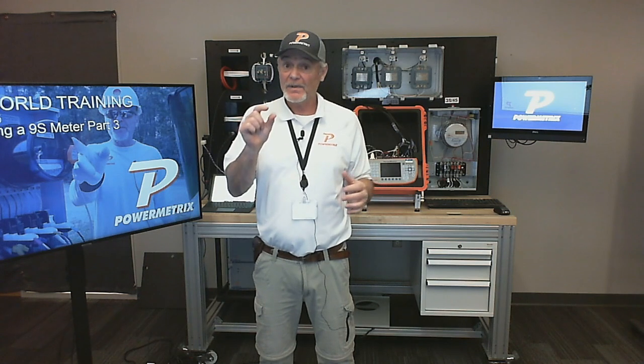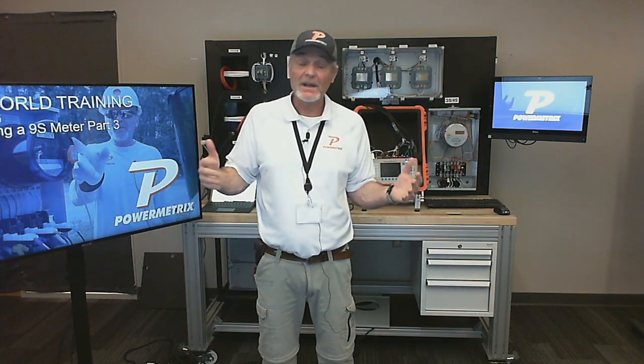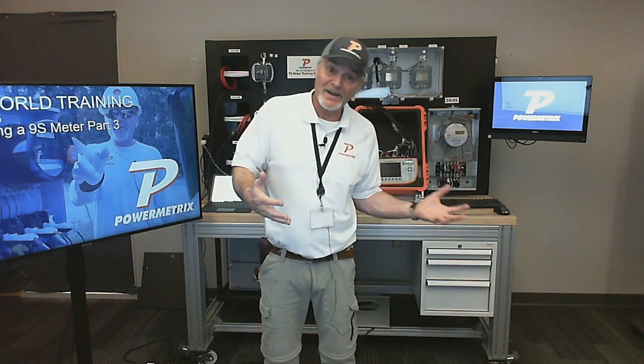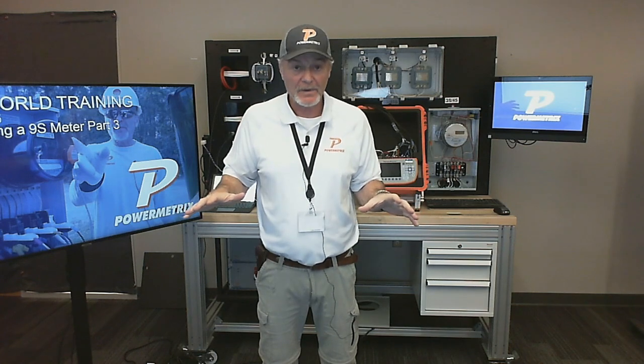So you've got a very low load. You should have at least 80 amps on those 800 to 5s according to ANSI to test them. Then you get in there and you've just got some lights or whatever, and you don't have nearly 80 amps. Well, now you're already behind the curve. It's just stuff we have to deal with all the time being out there doing our testing, right?